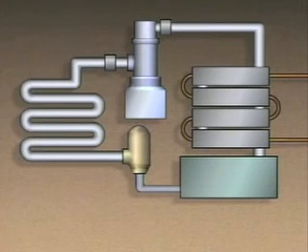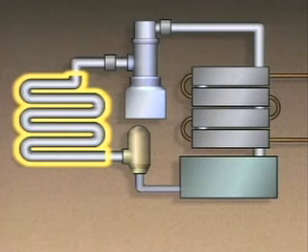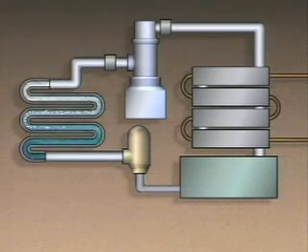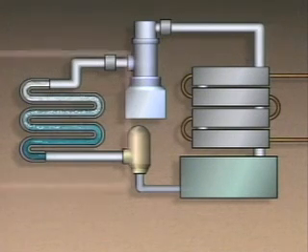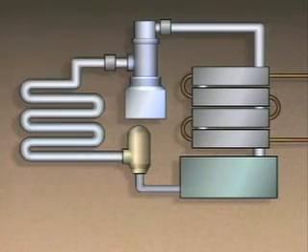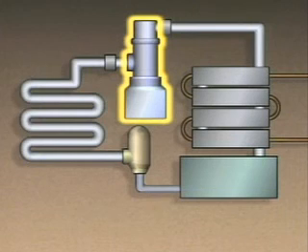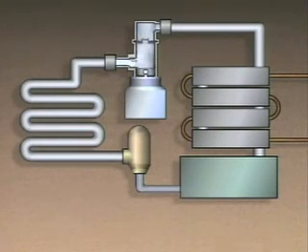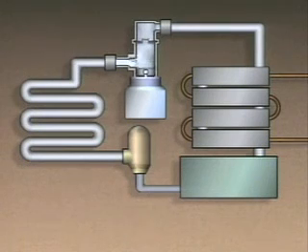Let's take a look at the components typically used to carry out these steps. In a vapor compression refrigeration cycle, the component in which the refrigerant absorbs heat is an evaporator. In the evaporator, the refrigerant evaporates or boils into a vapor, and the area around the evaporator is cooled. The evaporator draws heat from its immediate surroundings, and this heat is transferred to the refrigerant because the refrigerant's temperature is lower than that of the evaporator's surroundings. To move the refrigerant through the cycle, a compressor is used to add energy. The compressor receives the refrigerant vapor from the evaporator and compresses it into a relatively small space, increasing the vapor's pressure and temperature.